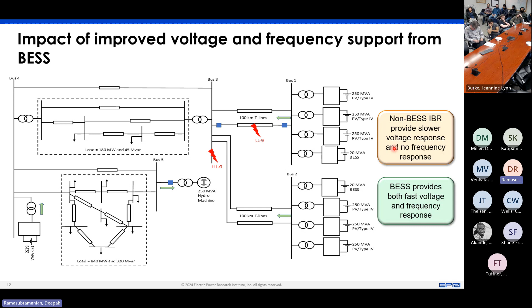So let's see what's the response to different types of events that we would see. So you would first have a double line to ground fault that you would apply at 5 seconds, followed by a triple line to ground fault that you would apply at 7 seconds in this particular network. So first you see that we are able to get robust fault ride-through in this high inverter percentage system, but not everything is going to be beneficial. There is a potential edge case that can come up where you could be triggering a voltage collapse. But the idea here is that by utilizing some of this additional capability from these inverter-based resources, you are getting the robust ride-through behavior, you're getting the fast response behavior.